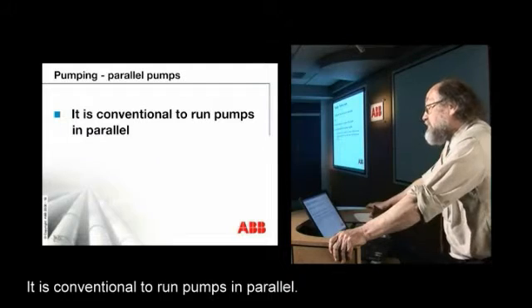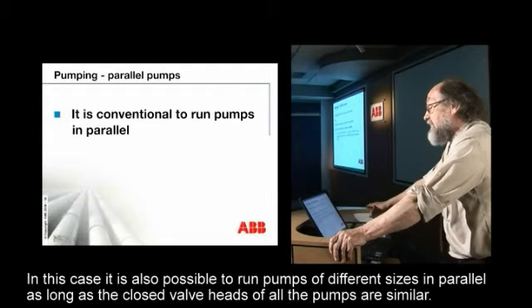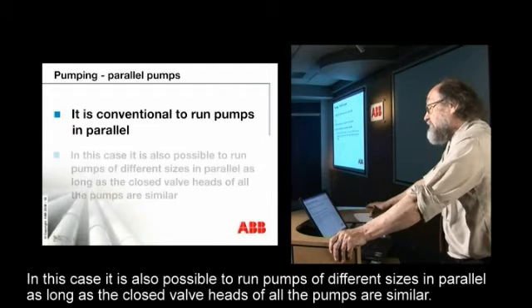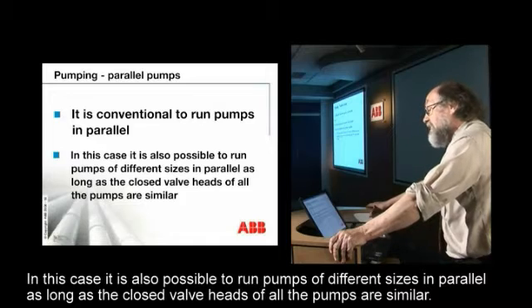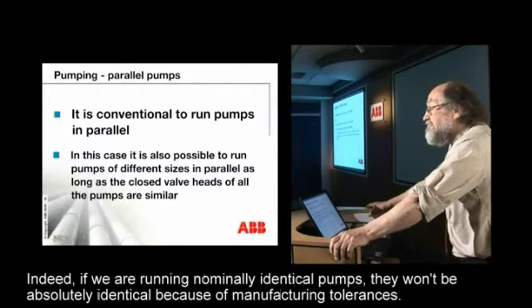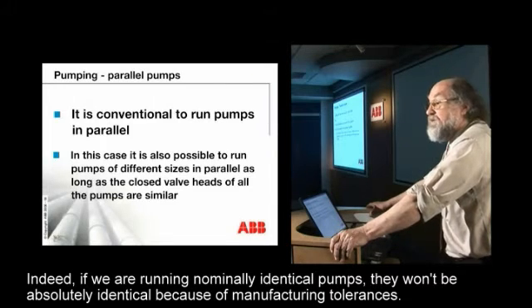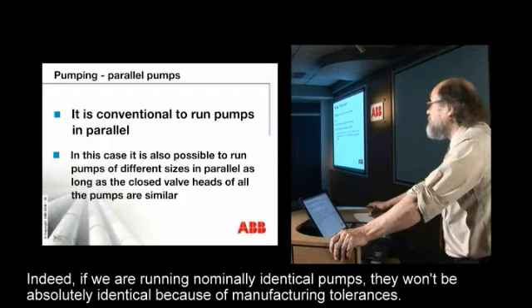It's conventional to run pumps in parallel. It's also possible to run pumps of different sizes in parallel, as long as the closed valve heads of all the pumps are similar. Indeed, if we're running nominally identical pumps they won't be absolutely identical because of manufacturing tolerances.